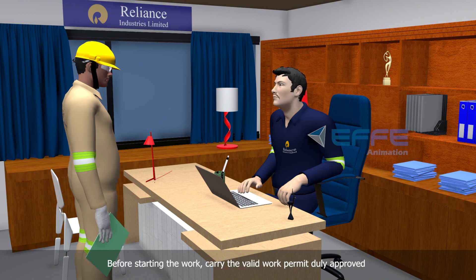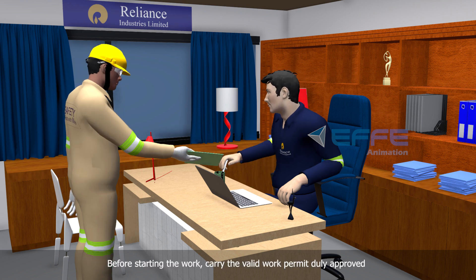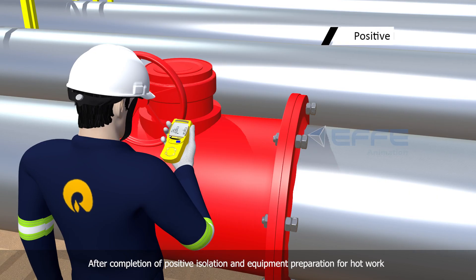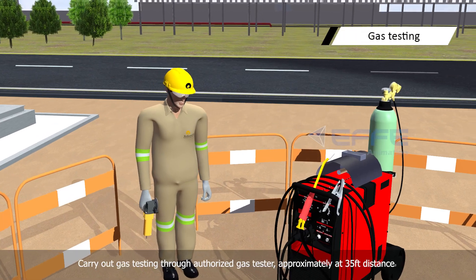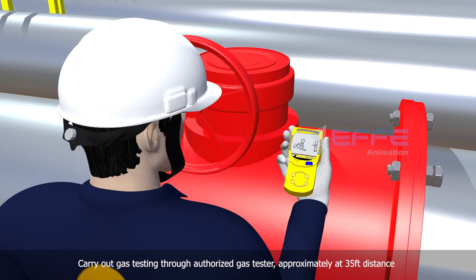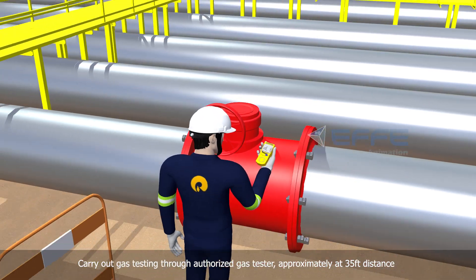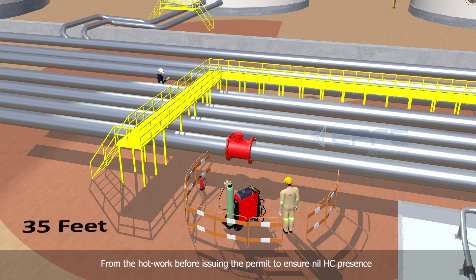The safe practices during hot work: Before starting the work, carry a valid work permit duly approved by the terminal manager, supported with a level 2 HITRA and CDR. After completion of positive isolation and equipment preparation for hot work, carry out gas testing through an authorized gas tester approximately at 35 feet distance from the hot work before issuing the permit, to ensure nil HC presence.